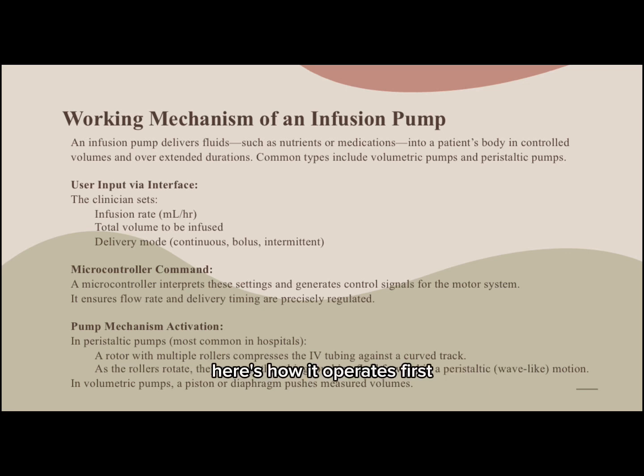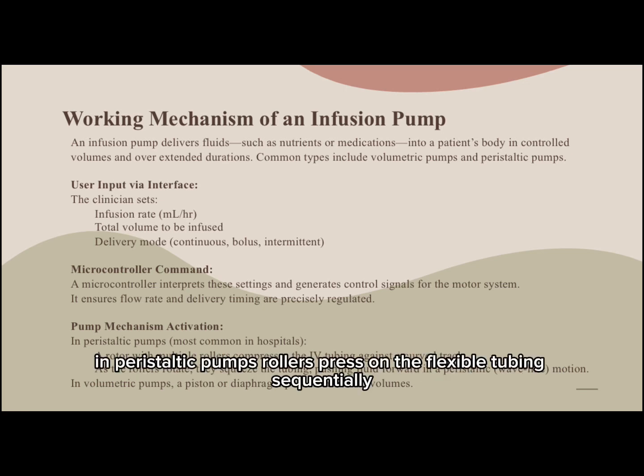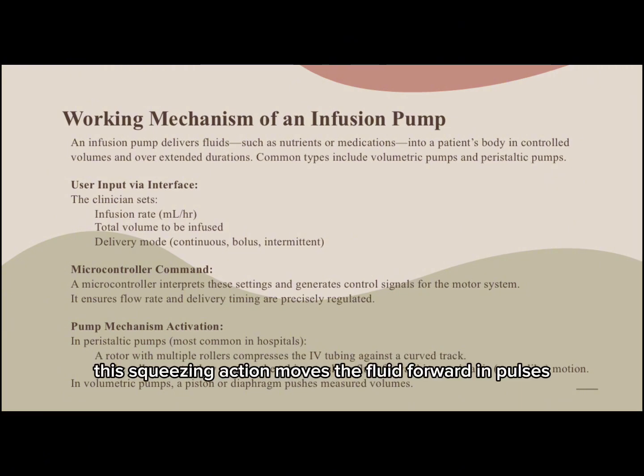Now, the working mechanisms of infusion pumps. Here's how it operates. First, the nurse or doctor programs the infusion rate, volume, and delivery mode into the control panel. The microcontroller processes these instructions and commands the motor to rotate. In peristaltic pumps, rollers press on the flexible tubing sequentially. This squeezing action moves the fluid forward in pulses but creates a nearly continuous flow, kind of like how our intestines push food forward, and that is why it is called peristaltic.